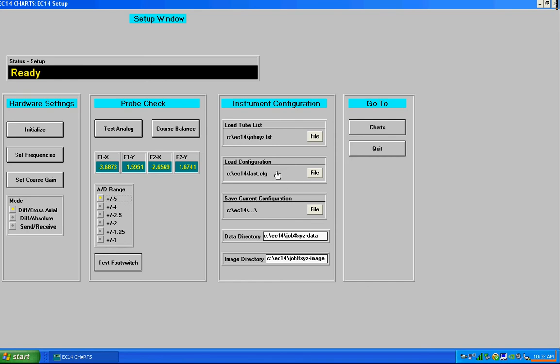So you've got a library of configurations for gains, frequencies, phase rotations for specific tube testing. You can load any one of those files up and the instrument will be ready to go for that particular tube. And then you can also save a current configuration.